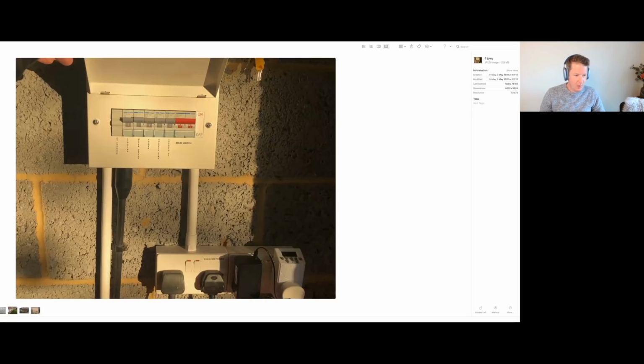So what we have to do is get more information from the customer, because unfortunately I don't think we're going to be able to run off this. We need to know what size is the feeder circuit that feeds this consumer unit back at the house, and what size is this cable - because if it's on a 63 amp back at the house, or 50 amp or something, that might be a possibility.